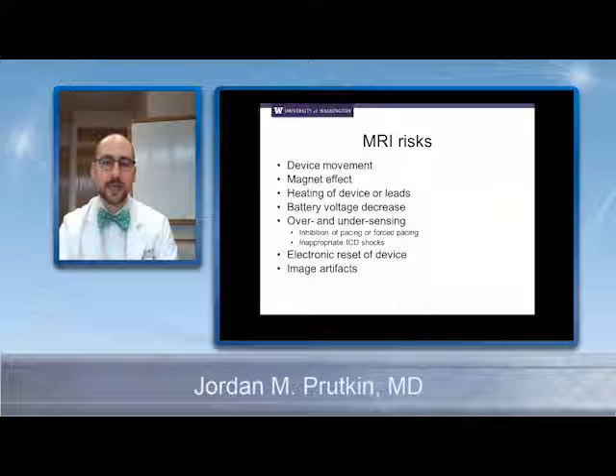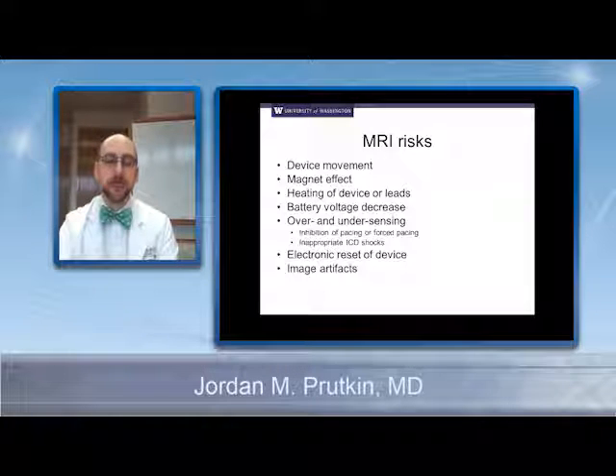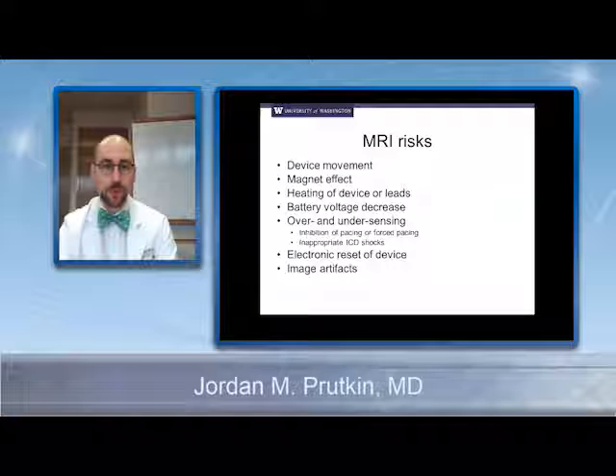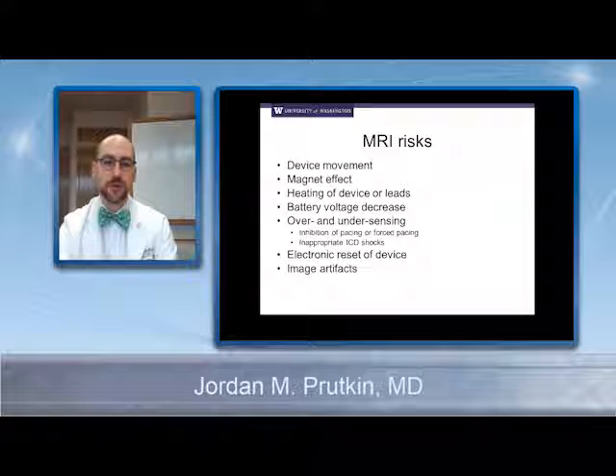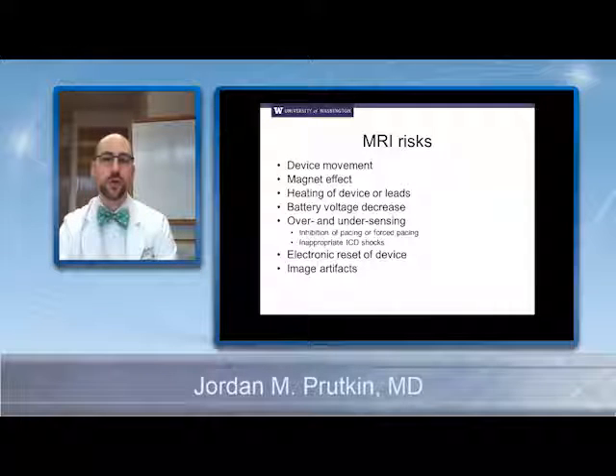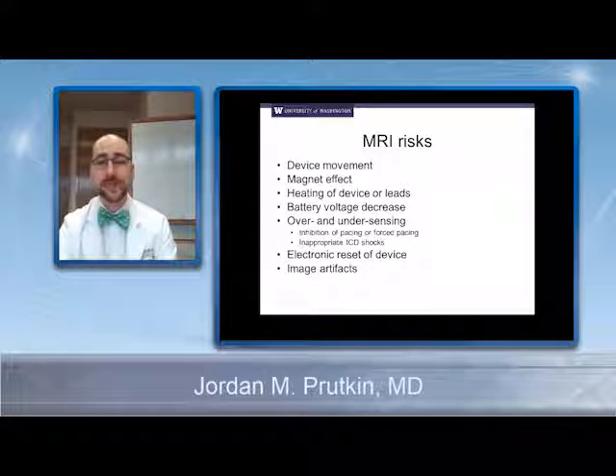And if you get heating of the leads and that energy is transferred all the way to the myocardium, well, that could be a big deal. You can see decreases in the battery voltage. The reason that is important is it can reduce the longevity of the device, which obviously is an issue. One of the big issues also would be concerns of oversensing or undersensing. So if that were to happen, you can either have inhibition of pacing, so someone needs pacing and it doesn't happen, or you force pacing. Someone who doesn't need the pacing, but you start to pace them, and you may start to pace them even in situations that are really quite rapid.